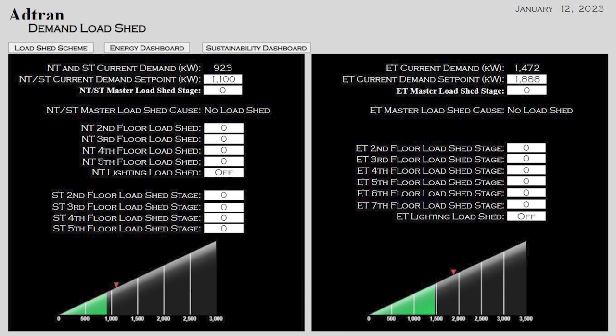So this is pretty much the main load shed screen. You can manually put in a certain floor in load shed, as well as completely disable a floor if you know that you have, like they had some major conference areas, and they knew if they had an event and they put it in load shed, they were about to have some angry people, so they were like, no, shut off that floor, let the other floors go into the load shed. So that gave the facility manager complete control over the load shed programming that we did. But if he left it alone, then all of those floors were looking at that master load shed stage, and all of it was controlling together.